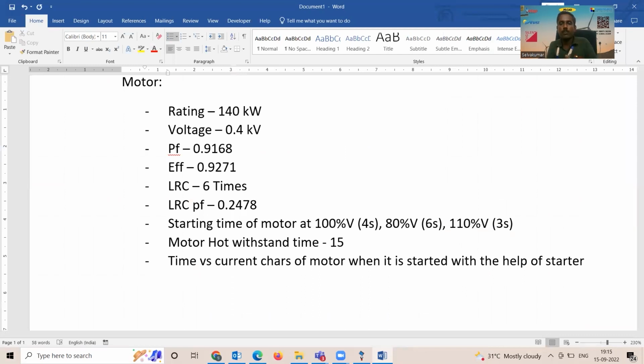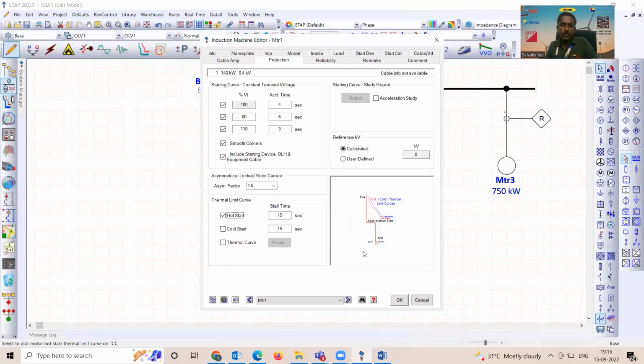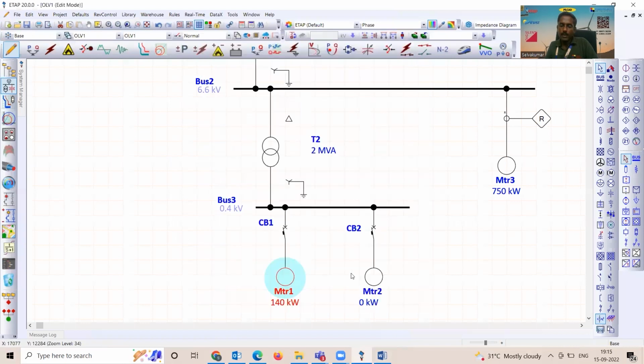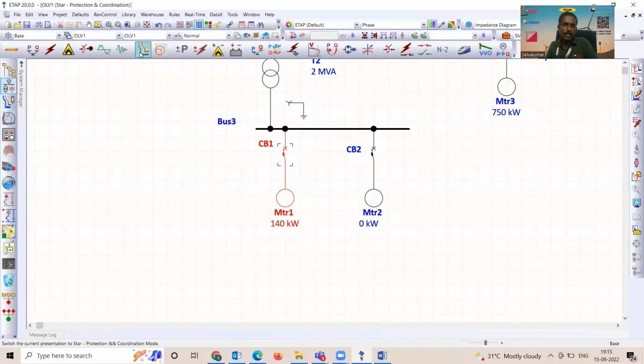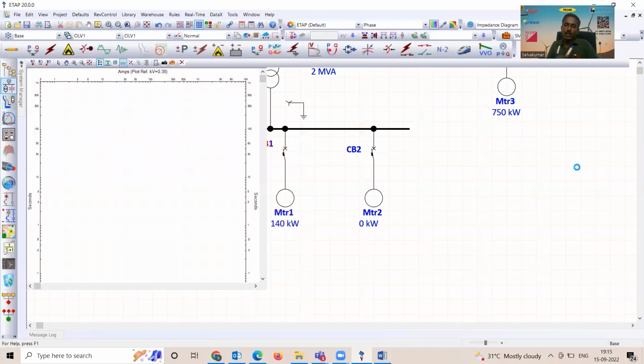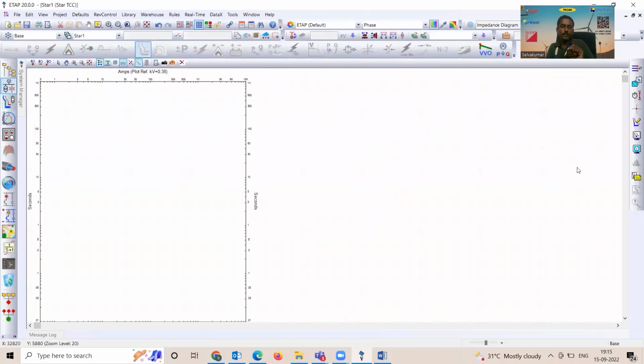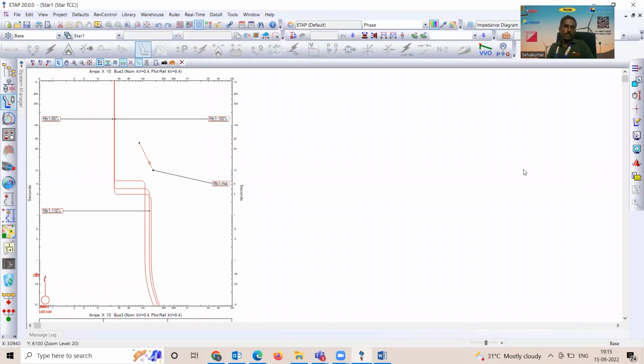When I say motor protection, it's overcurrent and earth fault protection. We are done. Let's pick up this circuit breaker, relay, release, whatever it is. In this case, it is a circuit breaker with the release, for the 140 kilowatt motor. Right. Now we got something.